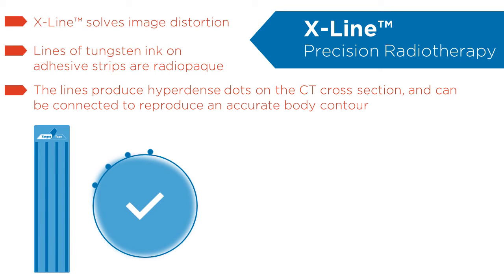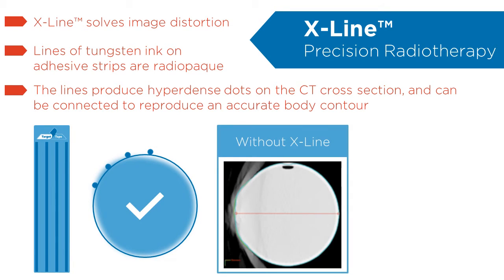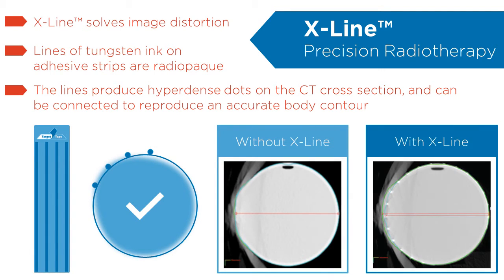Without X-Line, the cylindrical phantom appears distorted. However, with X-Line applied to the surface of the phantom, the true body contour can be reconstructed by connecting just underneath the bright, hyper-dense dots. By connecting underneath the dots, the true skin contour is identified, which avoids including these dots in the radiation planning.